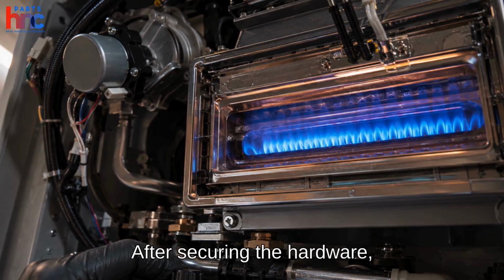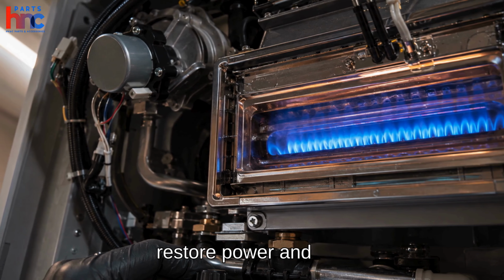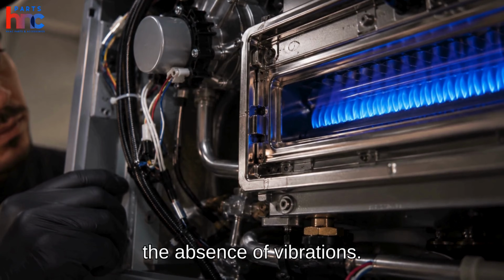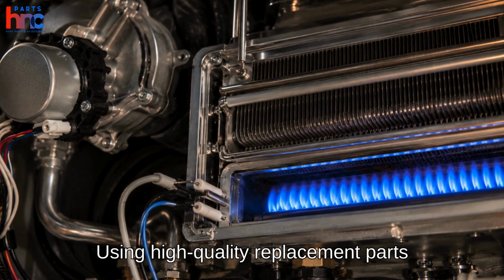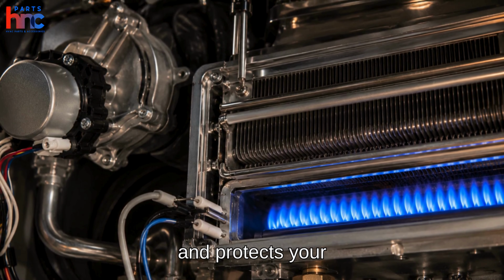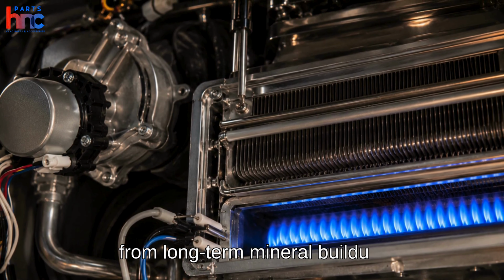After securing the hardware, restore power and gas to observe the startup. Monitor the first few cycles to check for flame stability and the absence of vibrations. Using high-quality replacement parts ensures a proper fit and protects your heat exchanger from long-term mineral buildup.